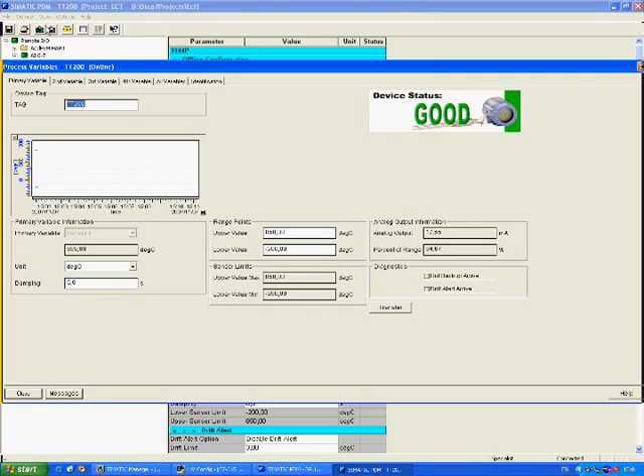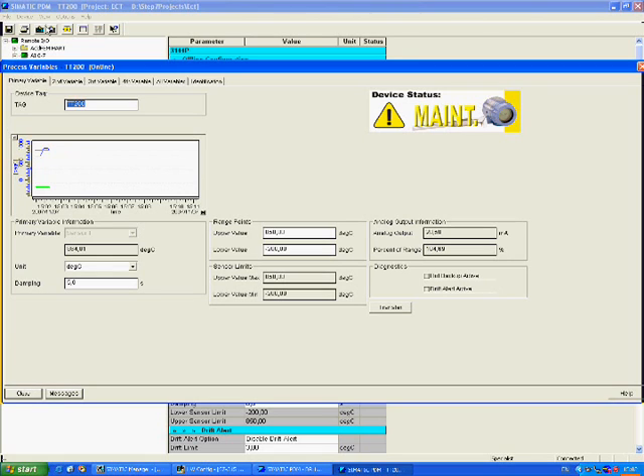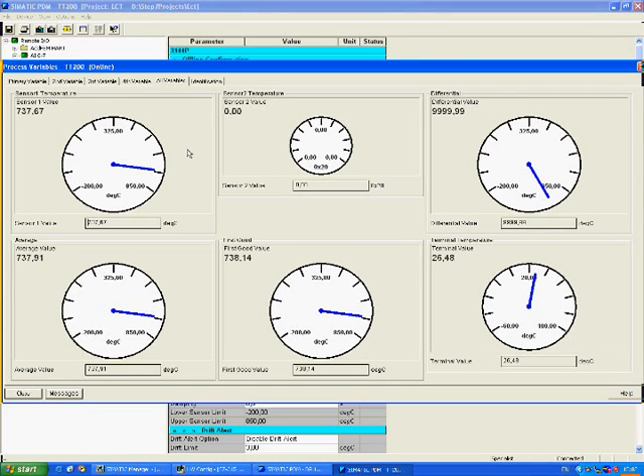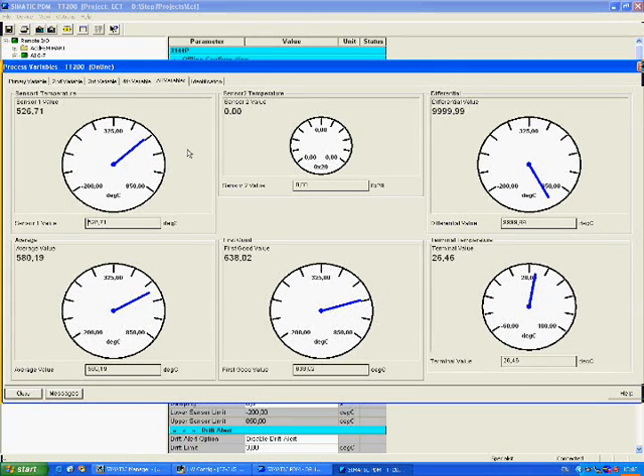As the process value increases and exceeds the range, the conditional image changes just as in the first system. As the process value decreases, returning within range, the conditional image changes back just as in the first system. Let's take a look at the other tab. The All Variables tab contains the same six dial gauges. In this system, the dials are 270 degrees. Again, note that sensor 2 does not have a value or unit because only a single sensor is connected. This second system shows exactly the same information — no information from the device is hidden. It is displayed as intended by the device manufacturer. EDDL is the key to interoperability.